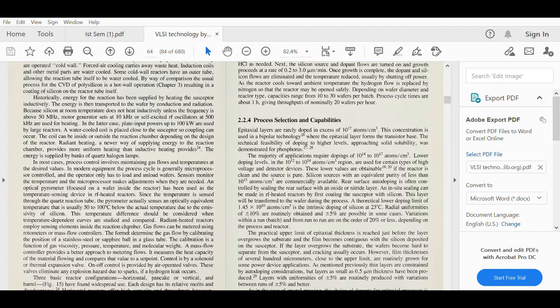Gas flows can be metered using rotameters or mass flow controllers. The former determine the gas flow by calibrating the position of a stainless steel or sapphire ball in a glass tube. The calibration is a function of gas viscosity, pressure, temperature, and molecular weight.